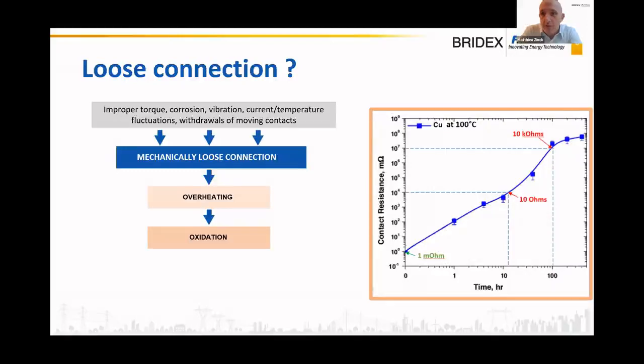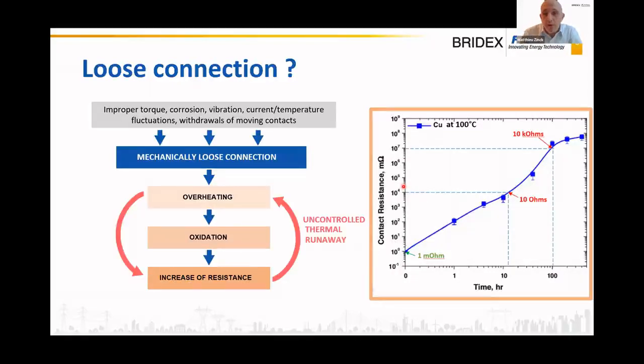If you take a copper contact at 100 degrees, which is written here, and you leave it at 100 degrees, which is basically the thermal limit that is given, for example, for terminals in Australia, 105 degrees. You leave it for a few hours, you can see that the contact resistance is increasing and increasing in a strong magnitude, including, for example, after 100 hours, 10 kilo ohm. So this is due basically to the oxidation phenomenon. And then you can see through the curve that basically you enter into a thermal runaway, and that generally leads to fire. So that's the most common scheme of fire and overheating happening.